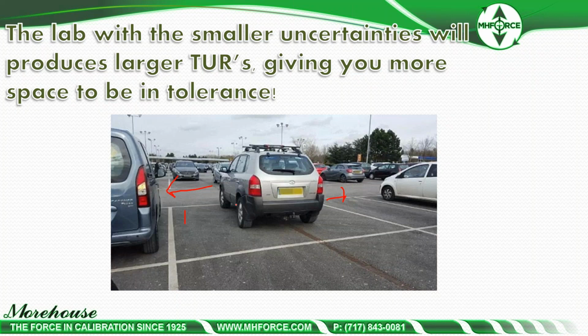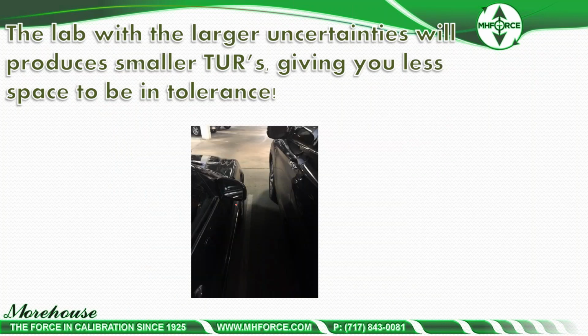I'm using that lab with the dead weight machine. I can be fairly confident that they're going to give me the best probability that when I receive my device back, I'm going to have that statement of compliance, and I'm not going to have to worry about recals and some of the other stuff that goes along with it. You compare that to a lab with the larger uncertainties, which will produce smaller TURs, giving you less space to be in tolerance. In this case, when I open this door, I'm going to have to suck in everything. I'm not as svelte as I once was, but I'm going to have to suck in everything and shimmy, and I'm going to have to be very careful.